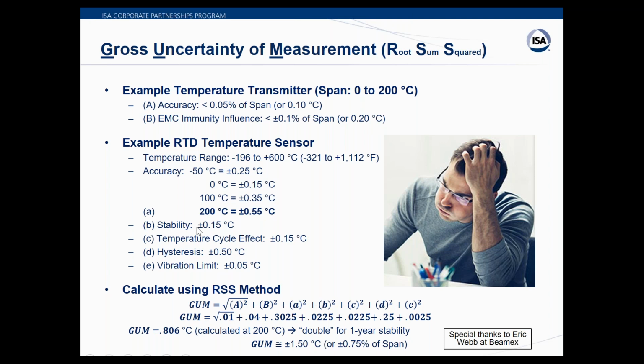So right off the spec sheet, we have stability. Now, again, I'm having a problem with this because it doesn't say 1 year or 6 months. Here's another factor, the temperature cycle. So as you go up and down, you're going to see differences. And here's that hysteresis. Now look at this. The hysteresis is as significant as the accuracy component. So again, Roy asked a while ago, if this is accurate to half a degree, can't we just go with that? But if your process goes up and down in temperature, it can potentially double what it measures. And then also vibration has an effect on the probe's output.